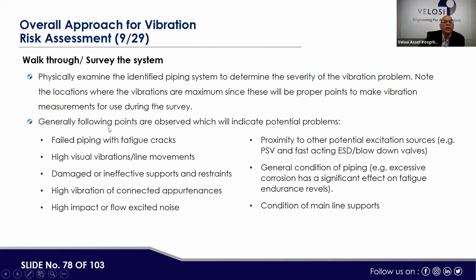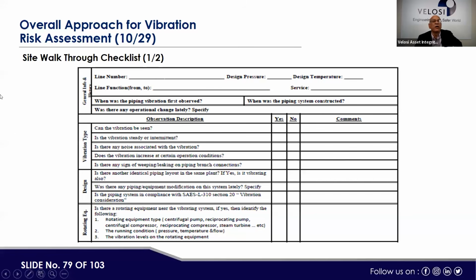during the survey. Generally, the following points are observed which will indicate potential problems: failed piping with fatigue cracks, high visual vibration, line movements, damaged or ineffective supports and restraints, high vibration of connected parts, then high impact flow-excited noise, proximity to other potential excitation sources, for example PSVs, fast acting ESD valves, then the general condition of piping, for example excessive corrosion has a significant effect on the fatigue endurance levels, and the condition of the main line supports also.